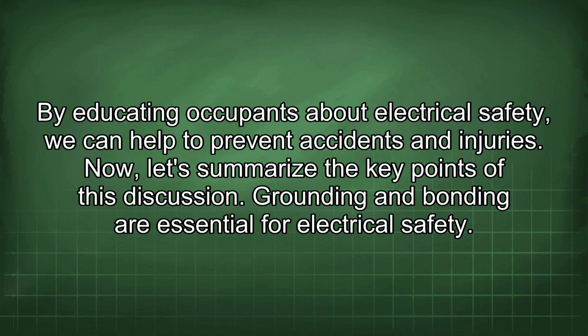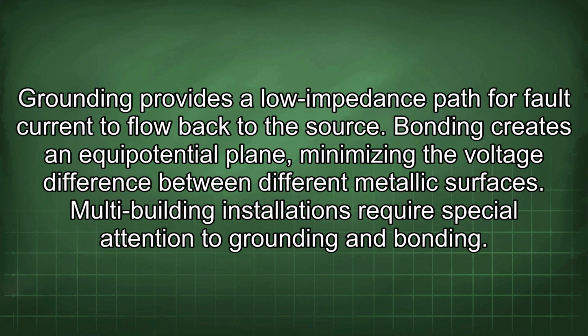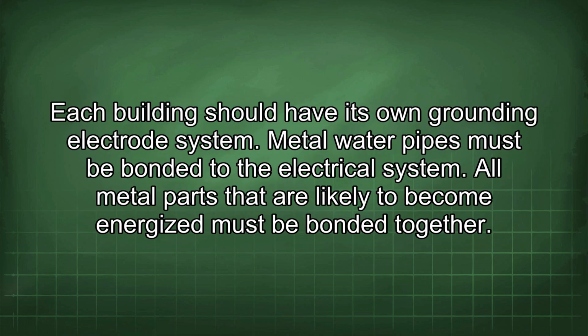Now let's summarize the key points of this discussion. Grounding and bonding are essential for electrical safety. Grounding provides a low impedance path for fault current to flow back to the source. Bonding creates an equipotential plane, minimizing the voltage difference between different metallic surfaces. Multi-building installations require special attention to grounding and bonding. Each building should have its own grounding electrode system. Metal water pipes must be bonded to the electrical system. All metal parts that are likely to become energized must be bonded together.